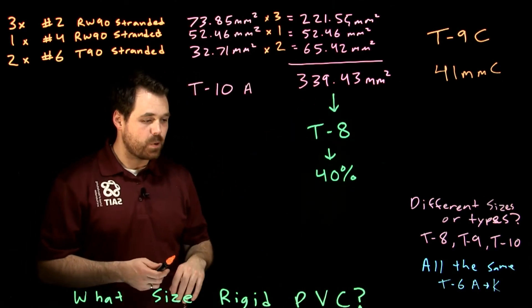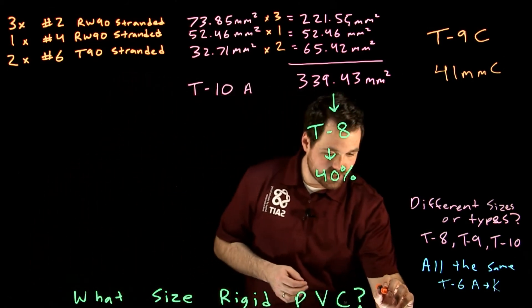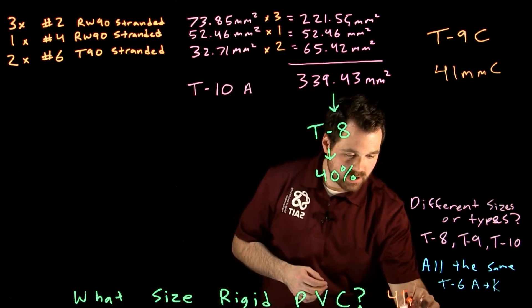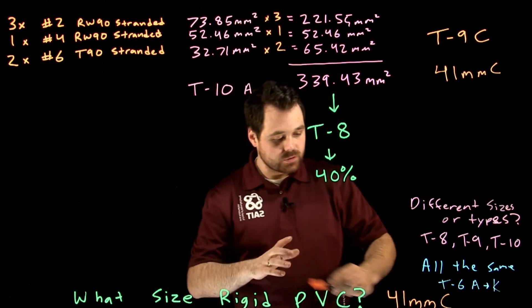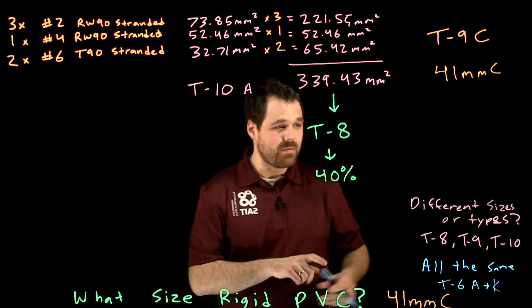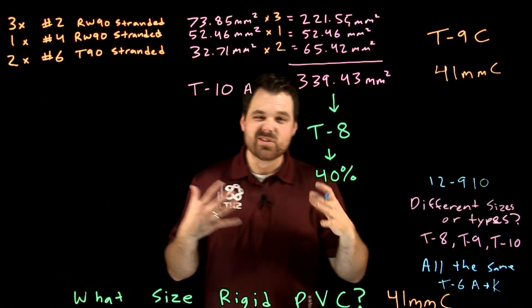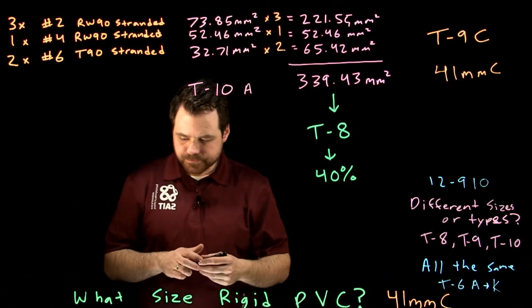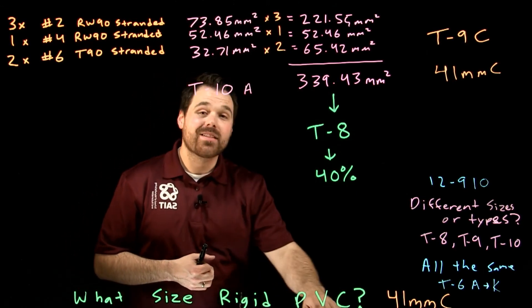So we have to use that forty one millimeter conduit. So, at the end of the day, we are going to have to get a forty one millimeter trade size conduit. So, just a reminder, all these rules come from section twelve wiring methods. Twelve, dash nine, ten is the rule that we're following here. Check out my other videos for some other examples. Thanks for watching.